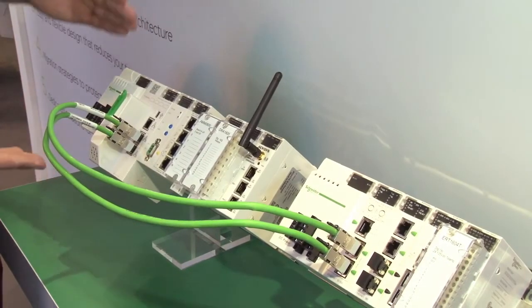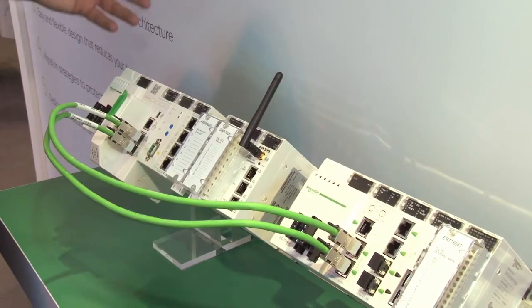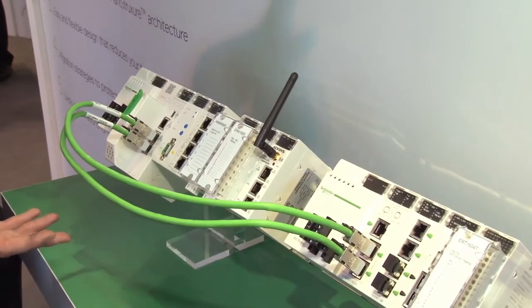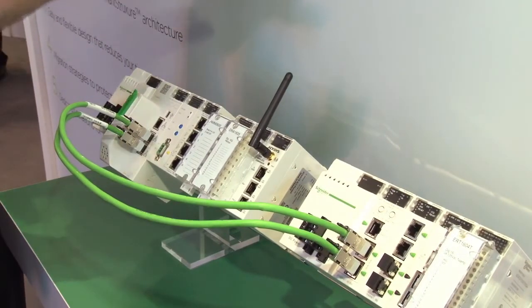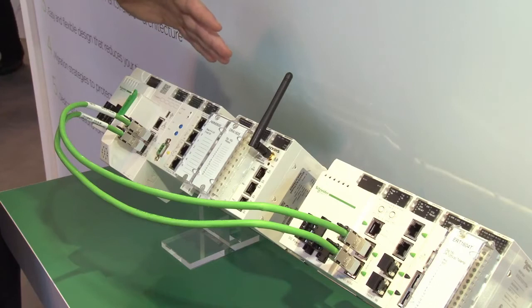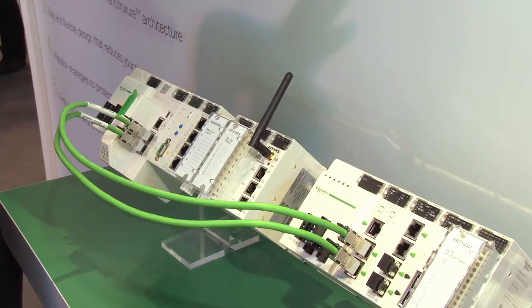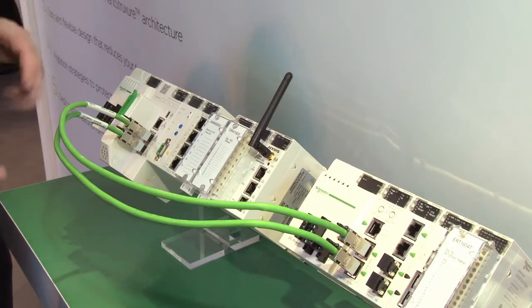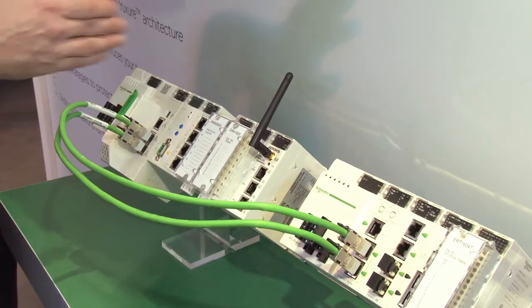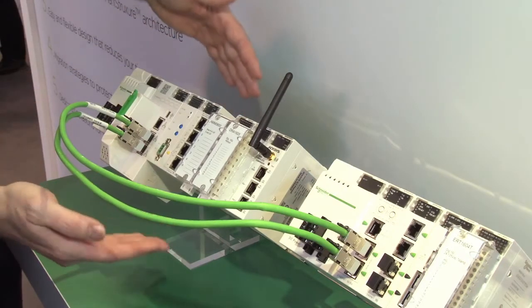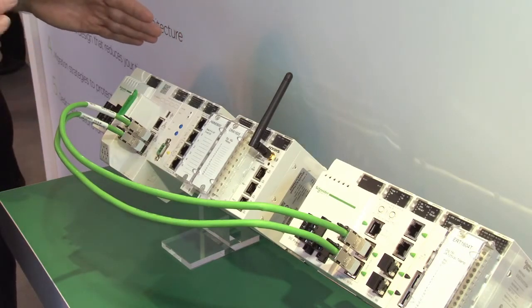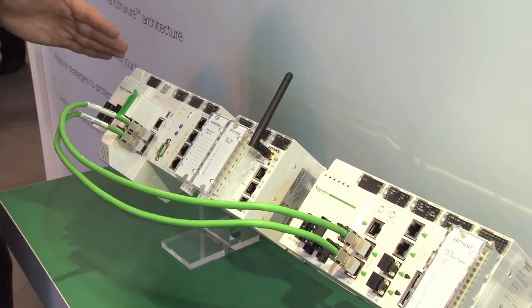The second key benefit of the Ethernet backplane is really down to performance. The fact that the devices are communicating on Ethernet means that there's a transparent exchange from source to destination. If you can take an example, let's consider we have a SCADA system upstream, maybe a HMI touchscreen, which is communicating through the PLC down to a variable speed drive on the factory floor, and we want to display process data, variable speed drive settings and so on. In an old-fashioned PLC, the request would go from the SCADA through the PLC, where it would need to be converted across the backplane to run across a different protocol, and then down to the drive, and then back again. So you have various bottlenecks and conversion points in the exchange of data.